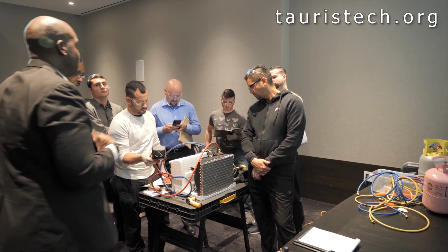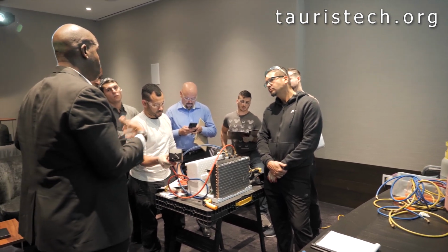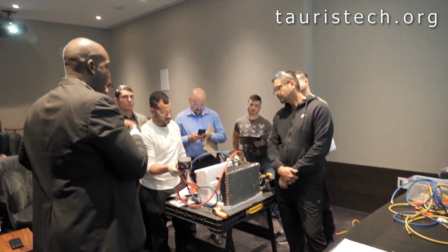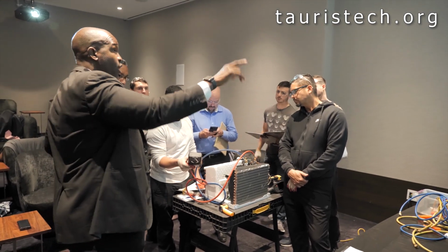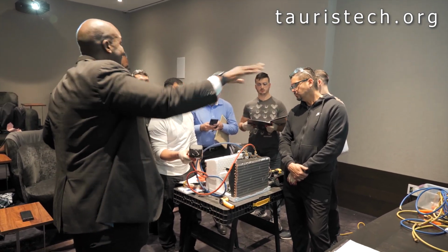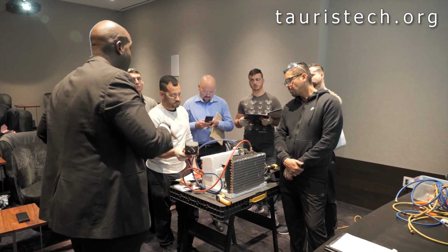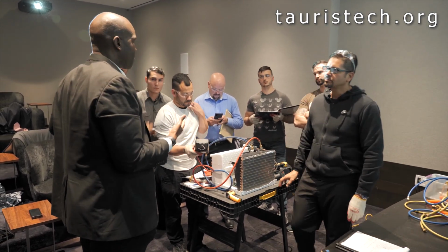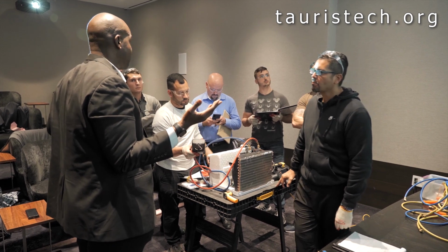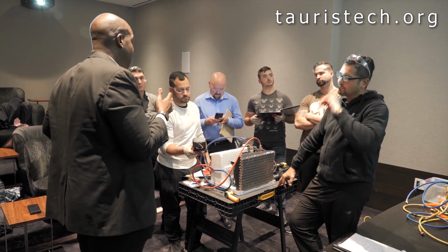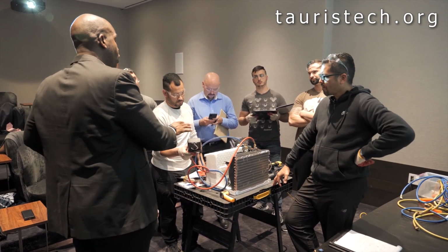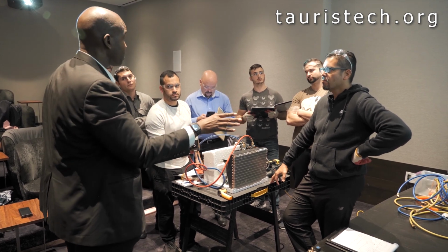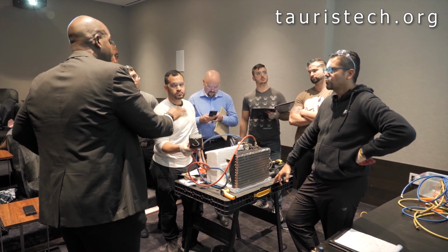If I have a machine that is running and I'm trying to determine what the charge is, what I am going on is what my saturation temperatures are supposed to be. So in a chilled water system, I have water, and I don't want to freeze it. Water freezes at 32 degrees, right?